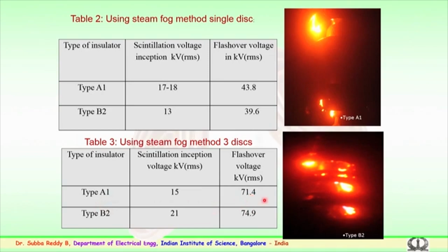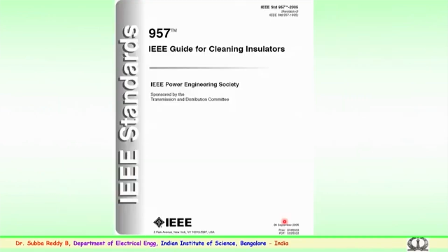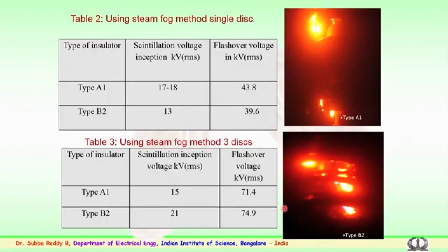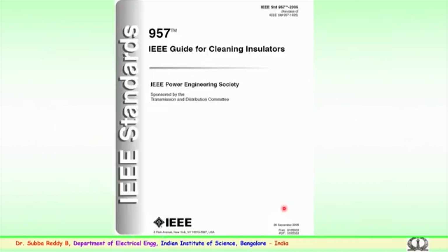So, these are some of the very important results, and I thought of sharing these results and comparing the values. Always a point to be noted: as the number of insulators goes up, the flashover goes up, but it is not a linear phenomena. That is the reason I have tried to show the values which have been experimented for various disc insulators. That was about the DC method for contamination or pollution testing which is followed in any standard laboratory before the insulators are used. So, we have discussed pollution on AC and the DC aspect.